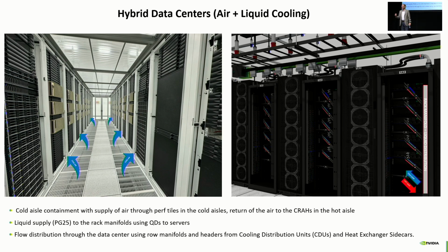We are bringing liquid very close to the source of heat, which is the GPUs in this case. GPUs can go up to and above a kilowatt, sometimes 1,200 to 1,500 watts, whereas a traditional CPU is about 100 to 150 watts. Now, as power increases for the GPU or CPU, if you continue with air cooling...